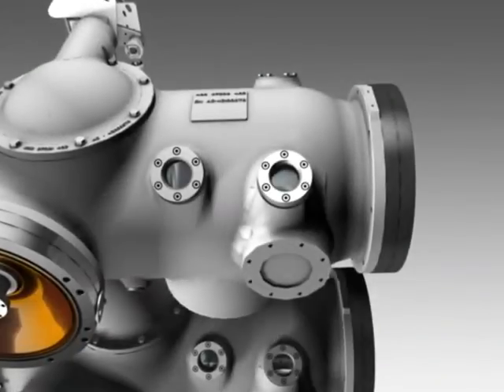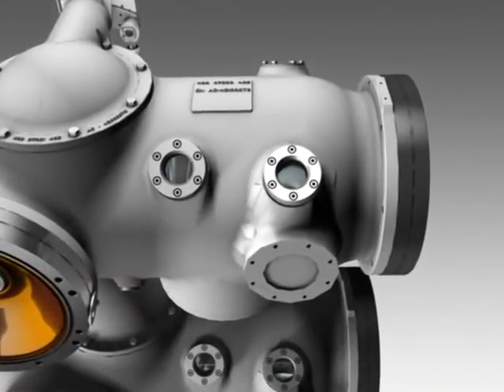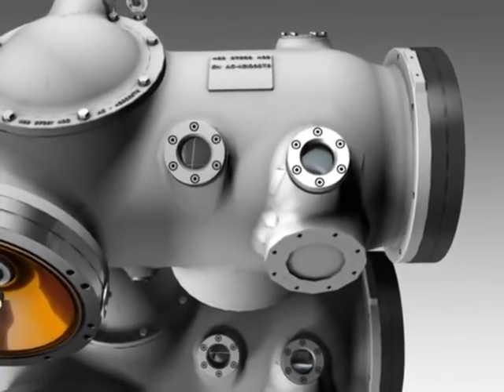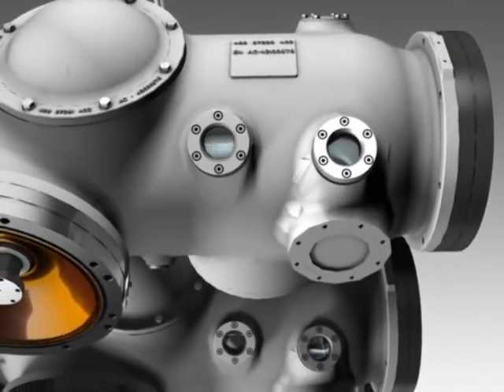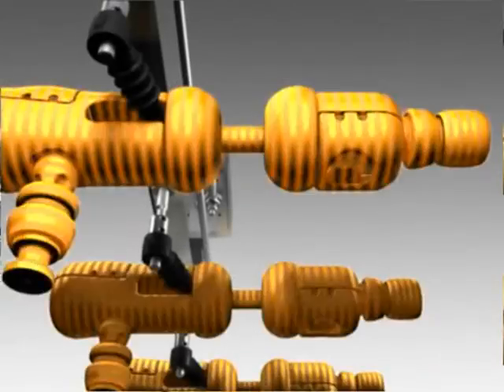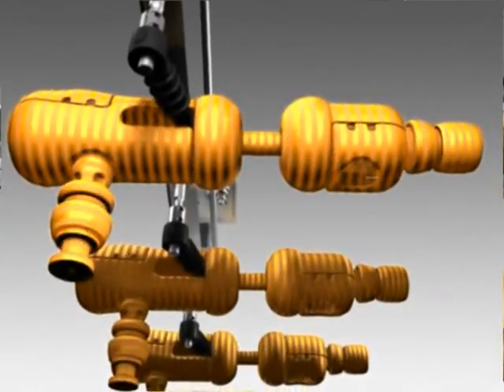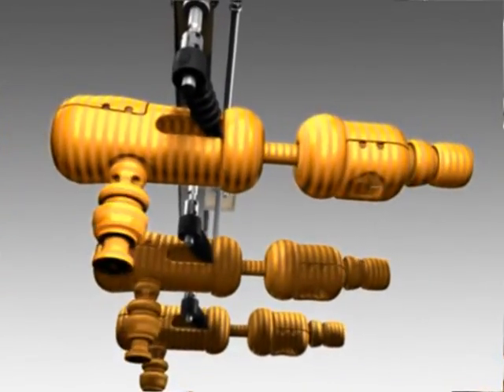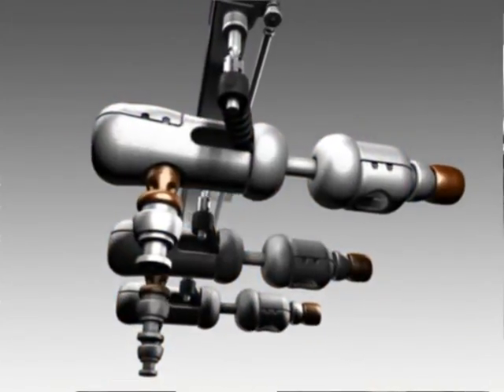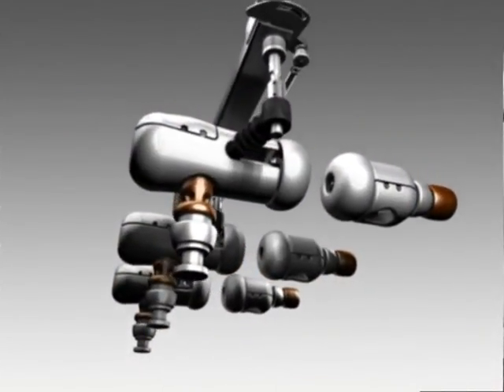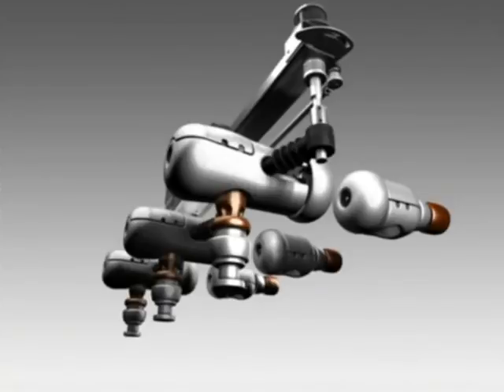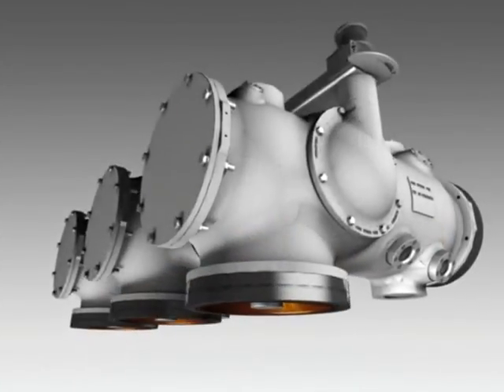Disconnectors create the isolating distances required for safe work on electrical installations. These switching devices are used as busbar disconnectors and as outgoing disconnectors. Disconnectors are of single-pole design. The 3 poles are jointly actuated by a motor drive via the operating linkage and a torque limiter.